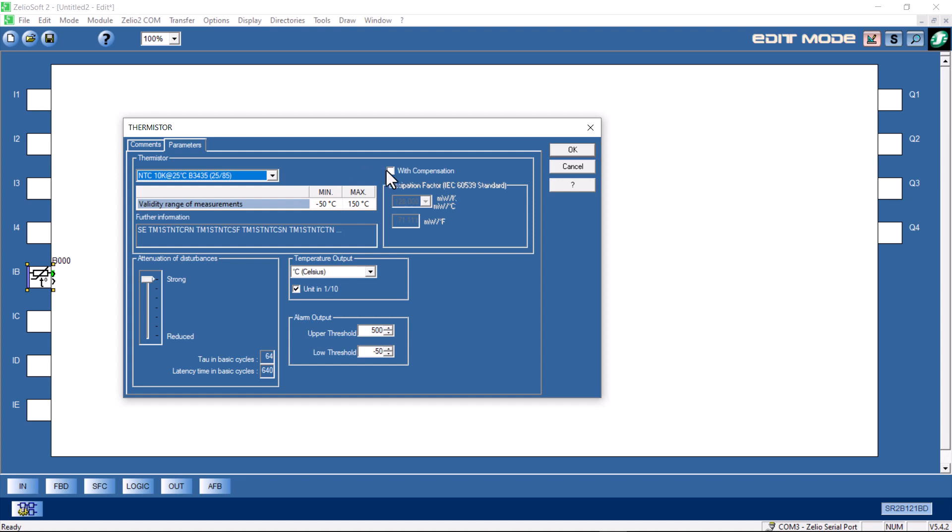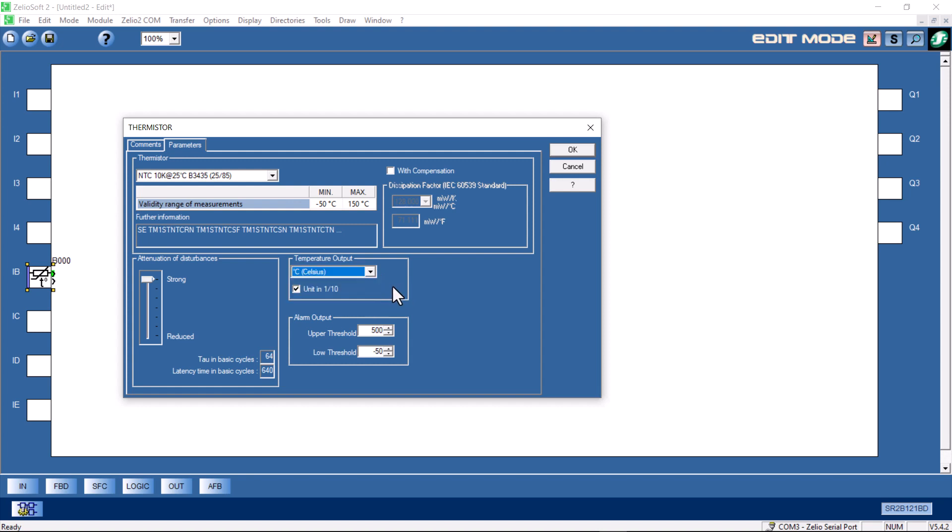Over on the right hand side, we can check the box for compensation. It allows the compensation for the actual temperature in the sensor changing itself due to the current flowing through it. You would need that in a very high precision application. In this case, we'll leave it unchecked. We can select Celsius, Fahrenheit or Kelvin. We can select units in one-tenth of one degree. I'll just uncheck that. We're just going to be measuring room temperature. But if you want to measure in tenths of a degree, then you would check that box.